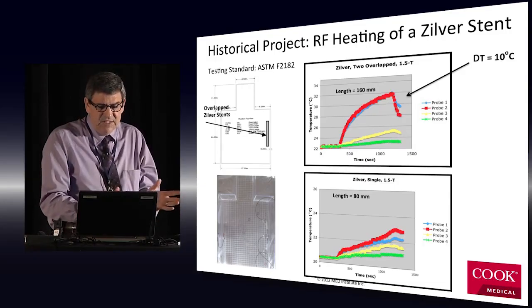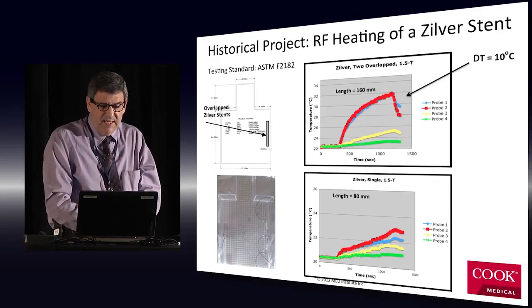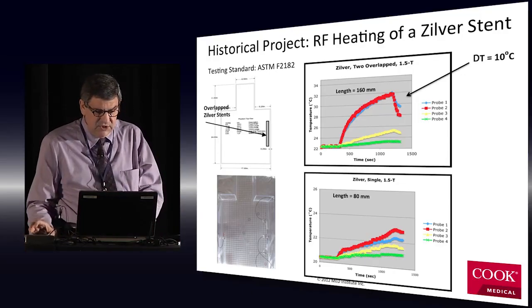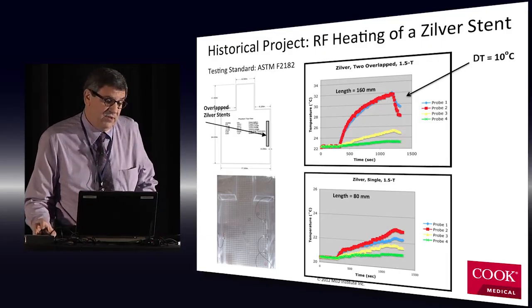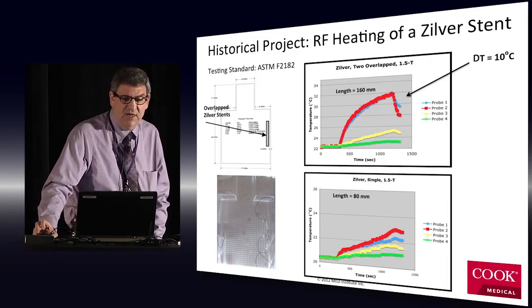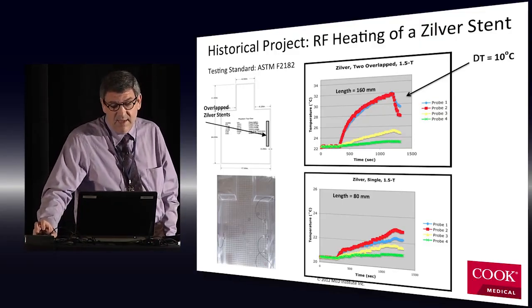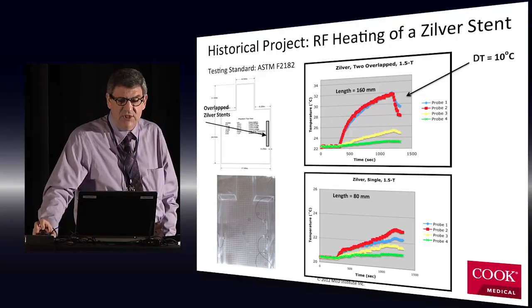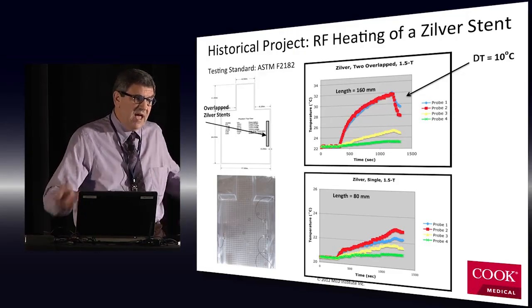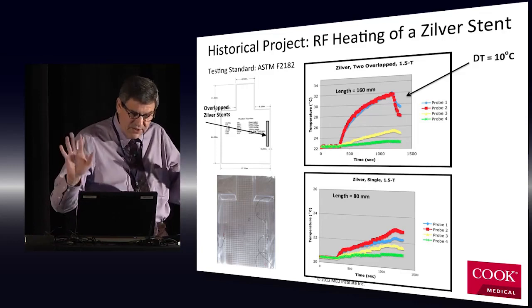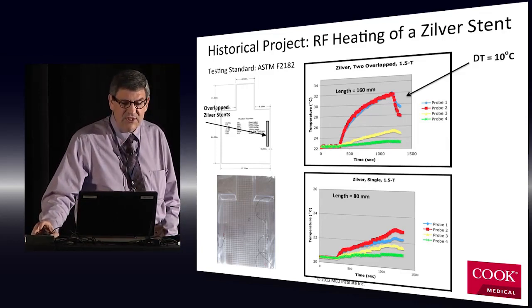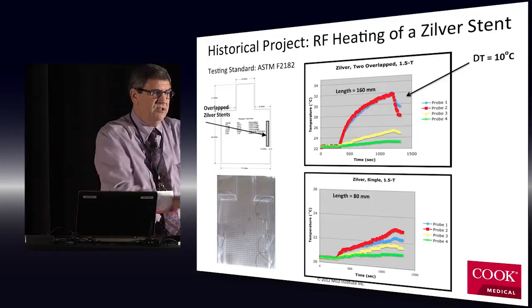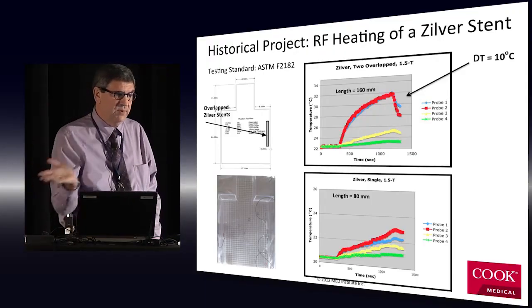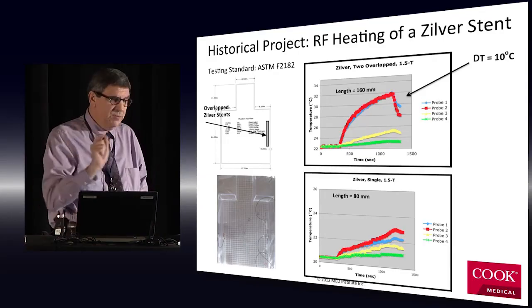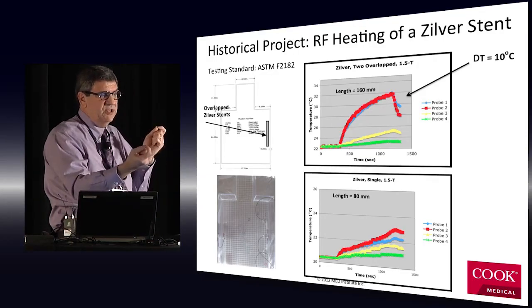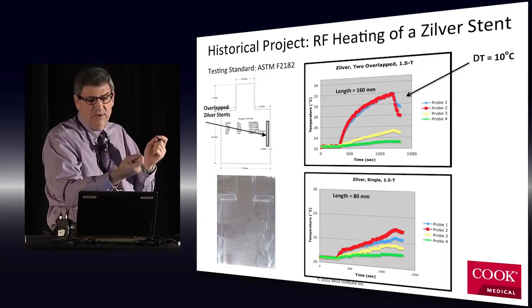And this problem came along in 2009, and you can see basically this is a phantom. It's a rectangular acrylic device that's supposed to be like a little head. And it's filled with a gel which has the electrical and thermal properties, dielectric properties, that are average tissue properties. We put our device in this phantom, put the phantom on the table, slid it into the MRI, turned on the RF coil for a typical scan time, and put thermocouples at the ends of the stents, because that's where we expect things to be the hottest. We'll cover more of that later.